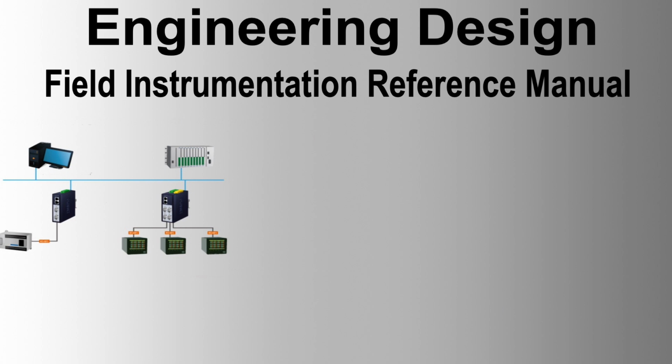Applications: used in industrial processes, HVAC systems, and laboratory environments for accurate and stable temperature measurement. Advantages: RTDs provide accurate and repeatable temperature measurements over a moderate temperature range. They are stable and have a long lifespan. Limitations: RTDs are more expensive than thermocouples and have a slower response time. They require a power supply and can be affected by lead wire resistance.